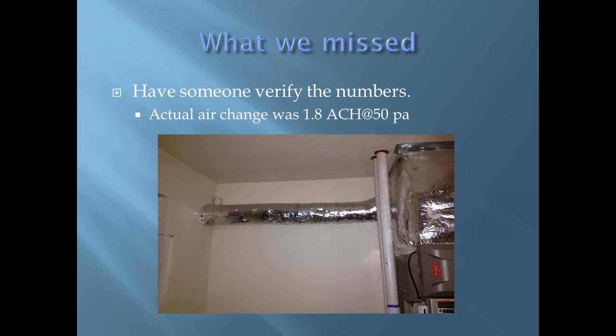So the question was, will the fresh air inlet take care of the other fans and neutralize the static pressure even when the furnace is not running? What I found was that as you turned the other fans on, it would make up only about 10 to 15% of that fan, and it will not reduce the static pressure by the same margin. So if the house starts out at -10 static pressure with all of the exhaust running, this will only bring it down to 8.5.